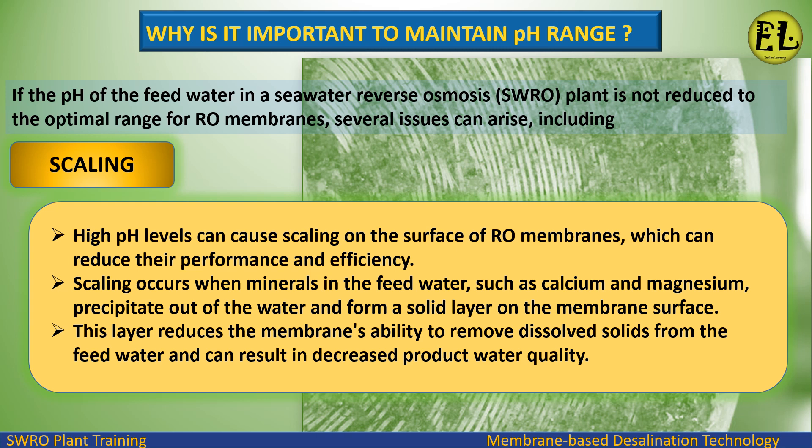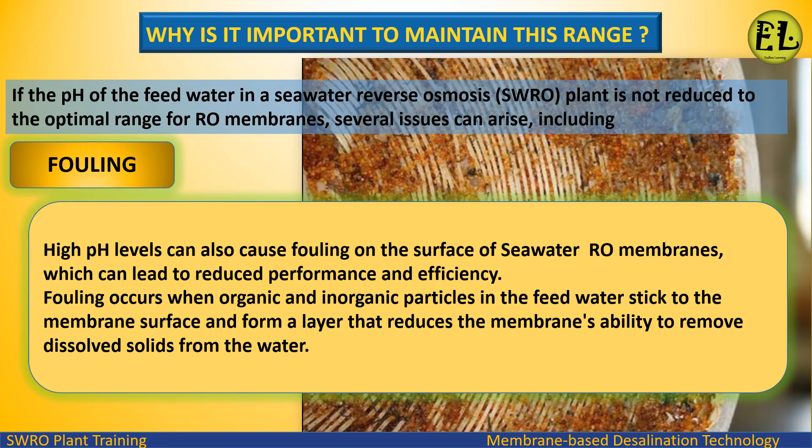Scaling occurs when minerals in the feed water, such as calcium and magnesium, precipitate out of the water and form a solid layer on the membrane surface. This layer reduces the membrane's ability to remove dissolved solids from the feed water and can result in decreased product water quality.